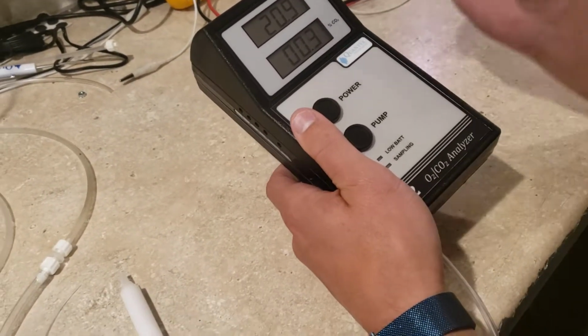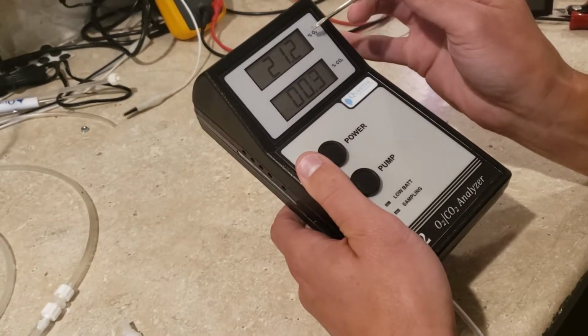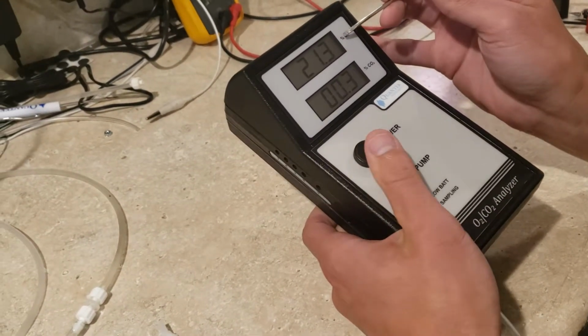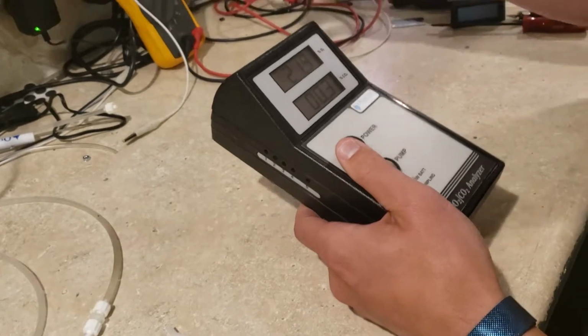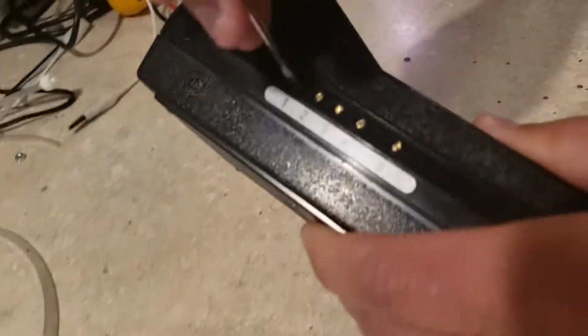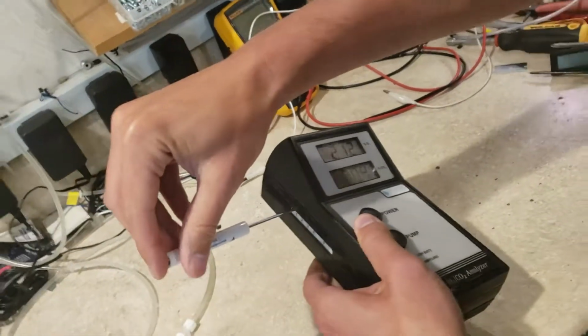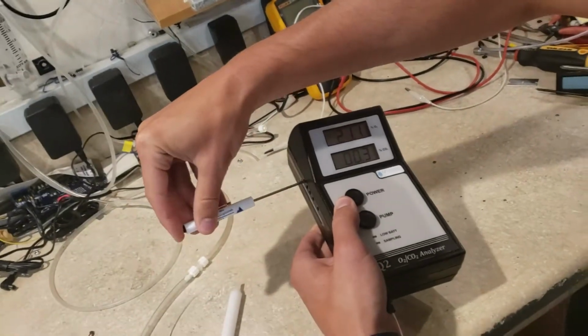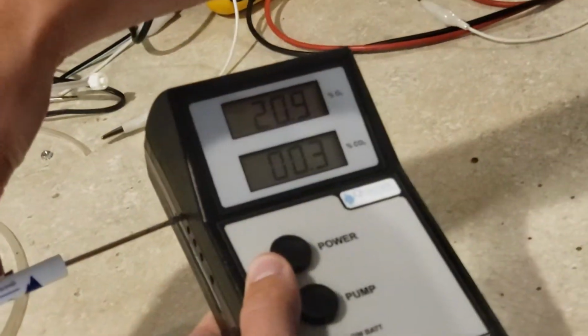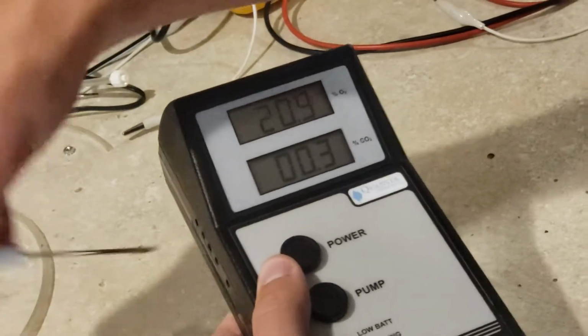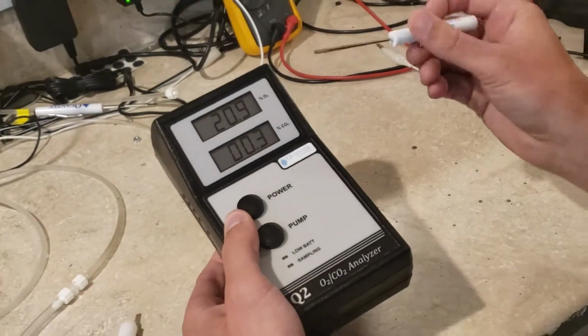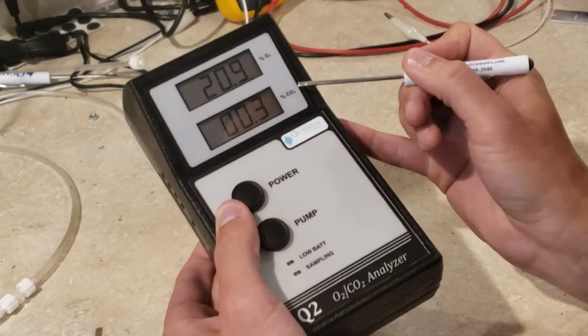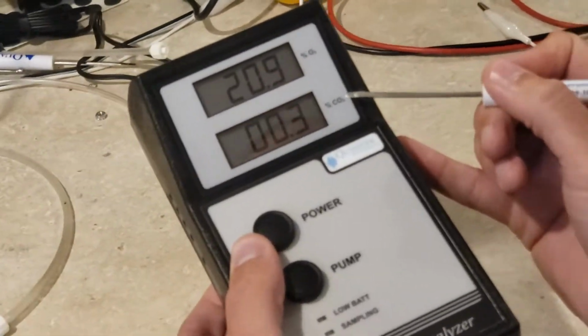So room air should read 20.9, and you can see that this is going slightly above that. So the way I'm going to adjust the oxygen is I'm going to go to the side here to this first potentiometer, and I'm going to turn that slightly down, and I'm going to watch the oxygen reading, and it's going to read 20.9. And so I know that that's set correctly. Also, the CO2 should read 0.1 or 0 in room air.